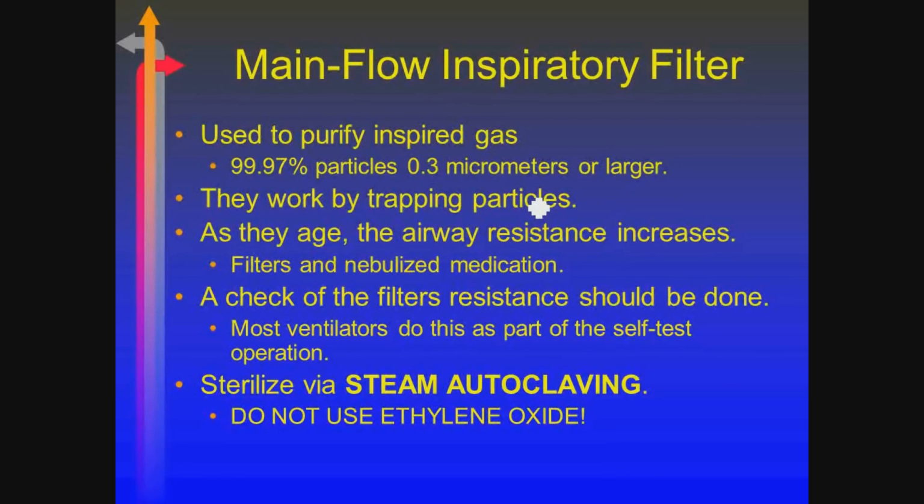Most of these main flow inspiratory filters are easily sterilized if they're reusable by using steam autoclave, and it'll say on the filter, it'll have that little 2 with a line through it, meaning it's a single patient use, or it won't, which means it can be processed. The process is steam autoclaving, not using gas sterilization with ethylene oxide. Key part.